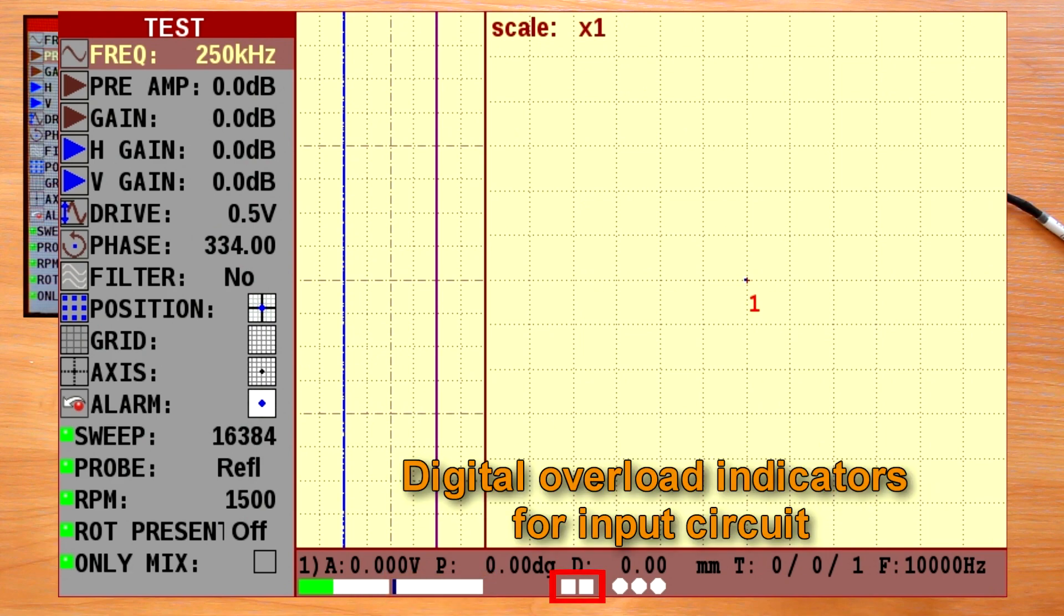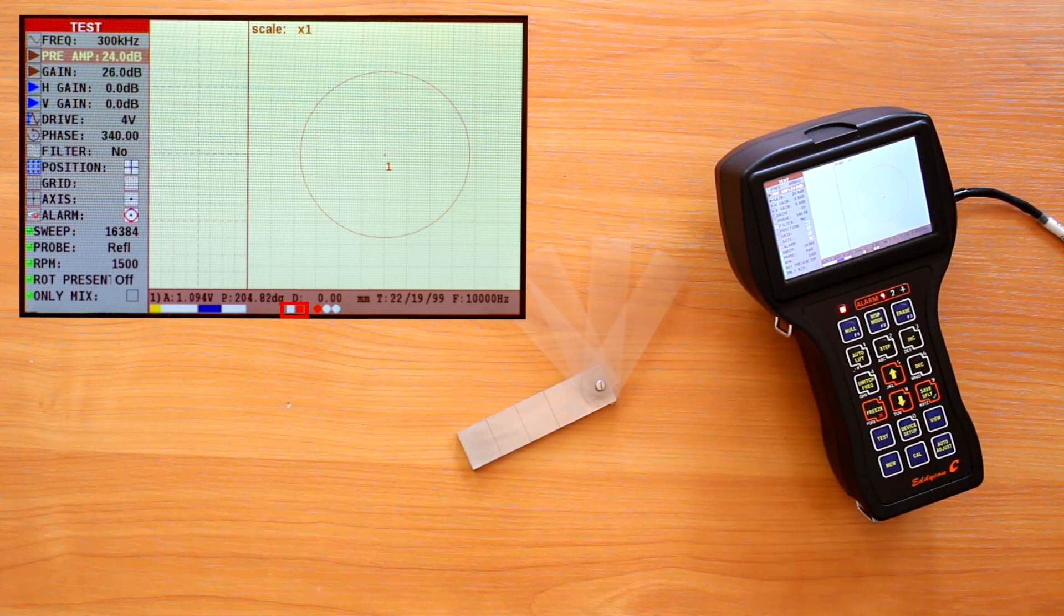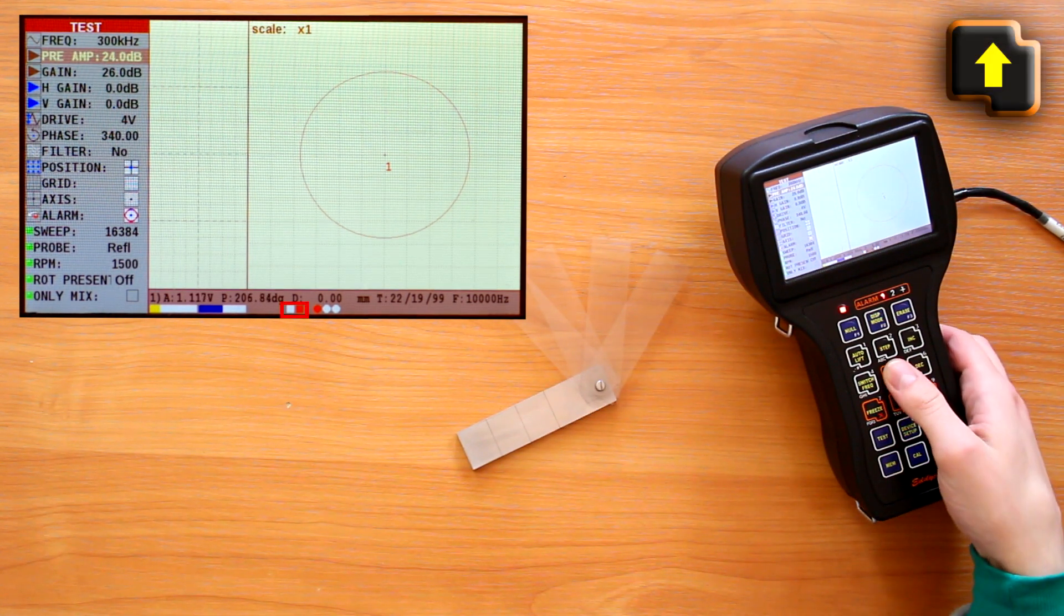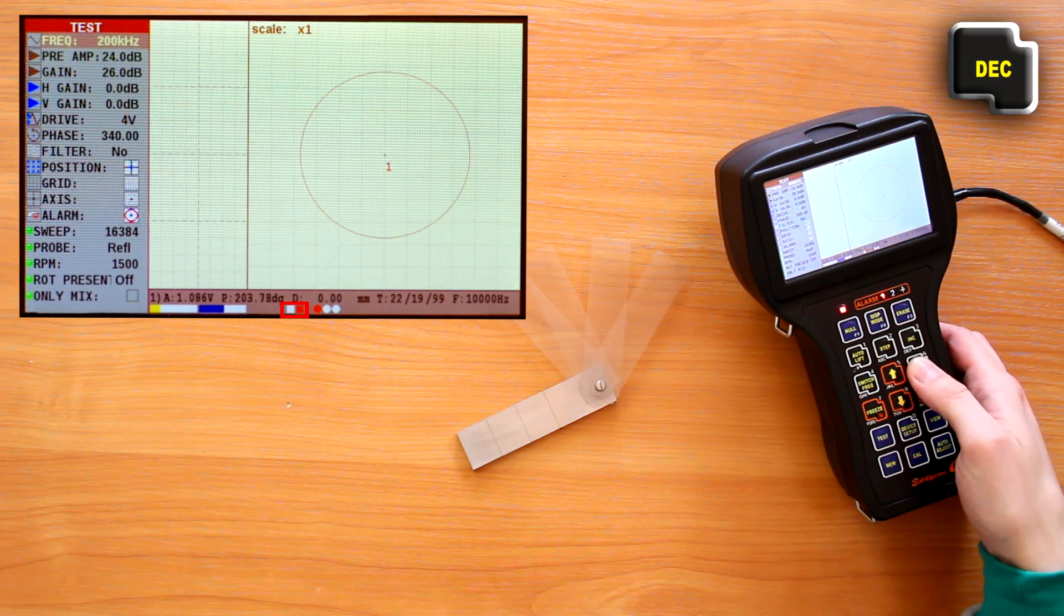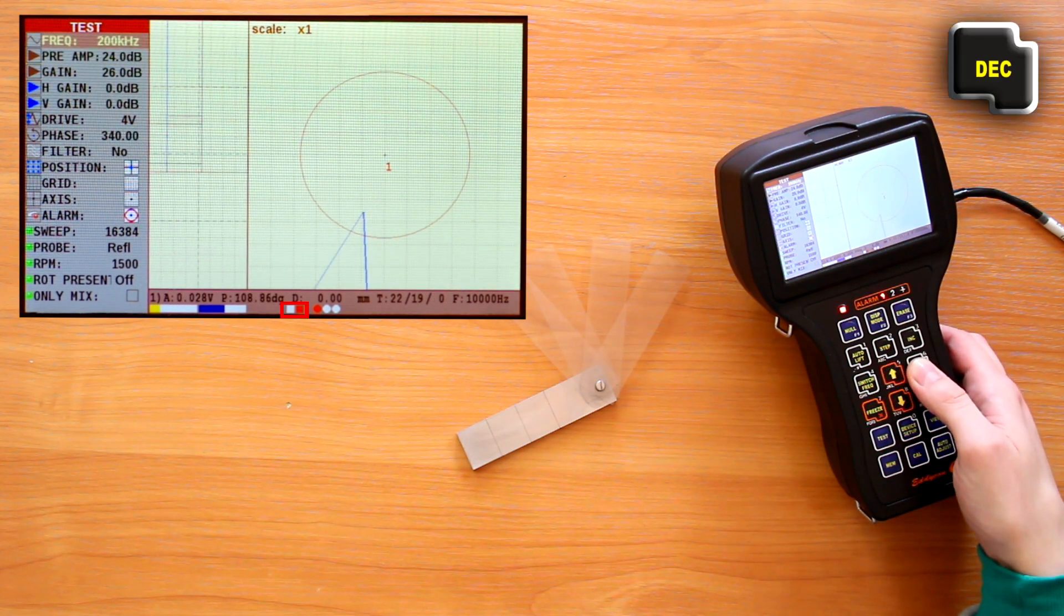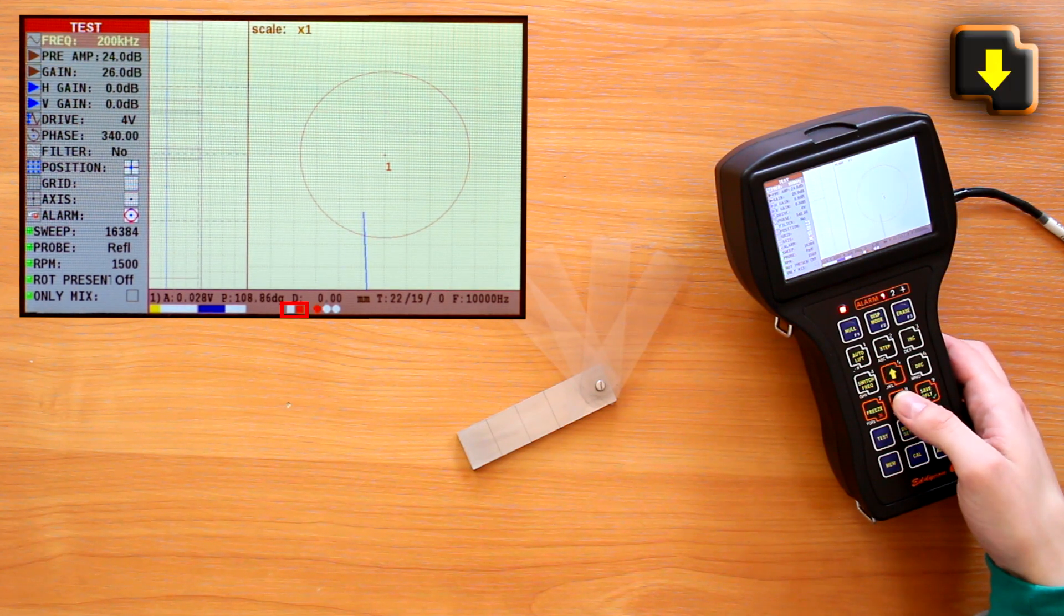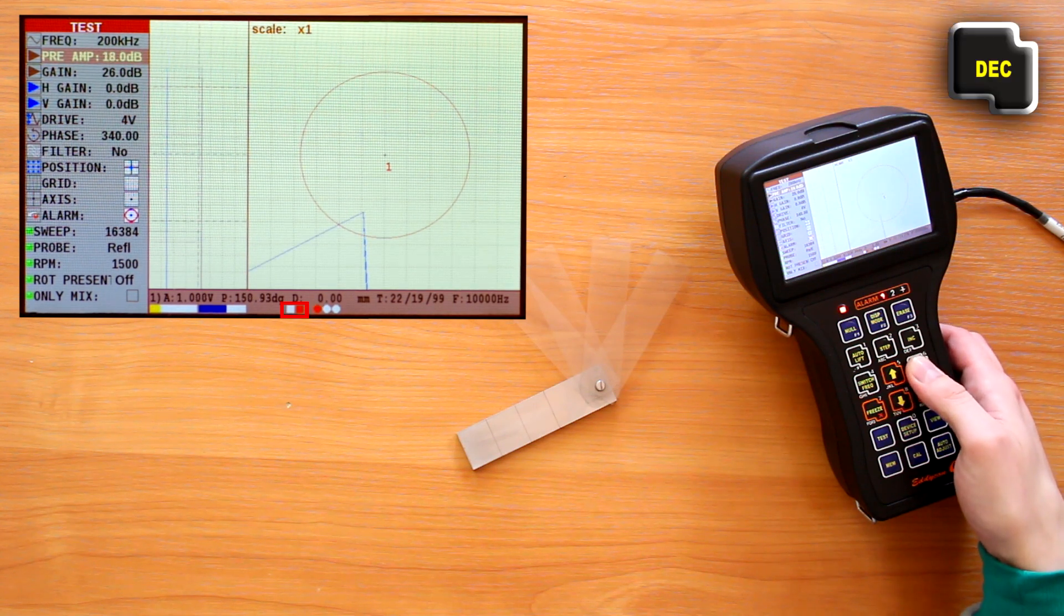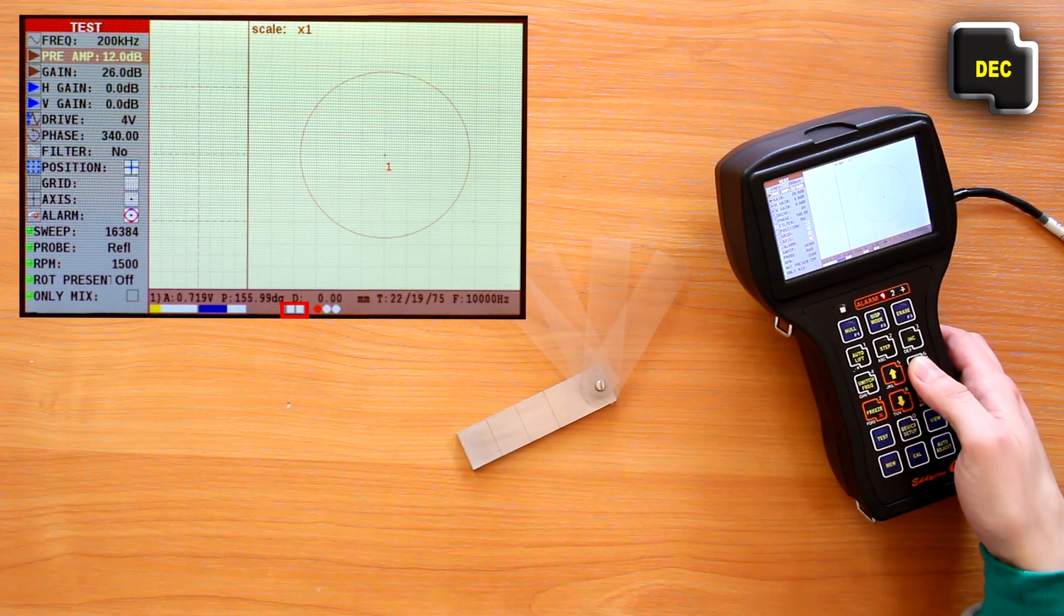Digital overload indicators for input circuit light up red when the input circuit is overloaded. In this case it is necessary to check whether an appropriate frequency value is set for the given ECP, and if this doesn't help, reduce the drive voltage and the gain if necessary.